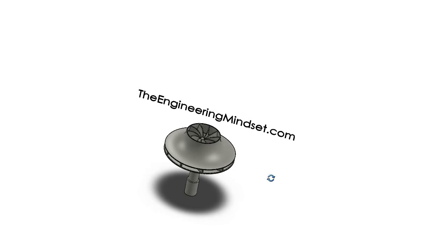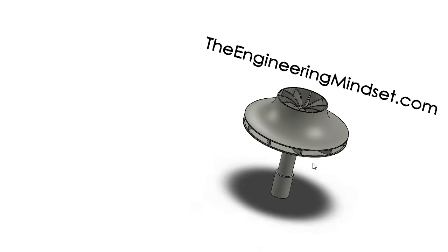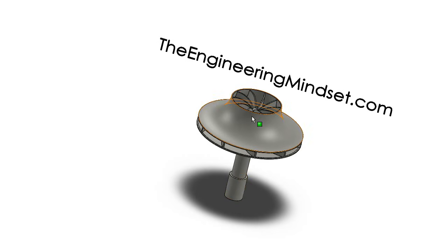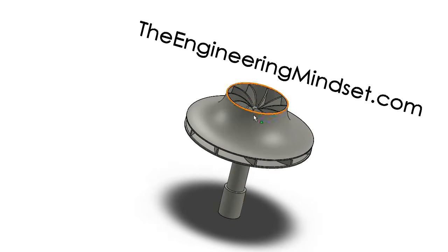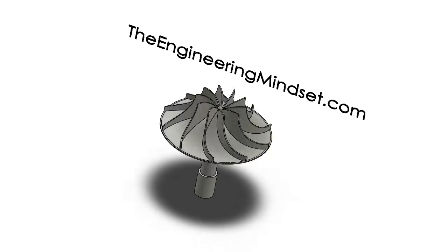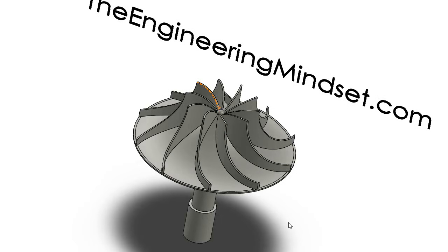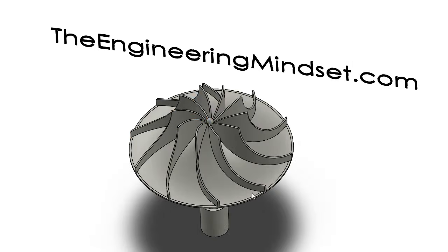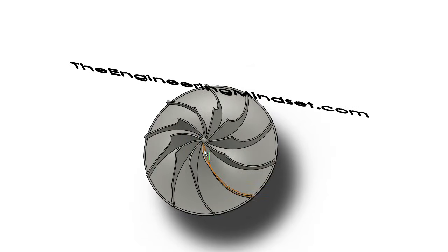If you look at the impeller here, so you can see we've got the gear mounted on the bottom of the shaft there, and at the top we've got the inlet or the flow area, and then we've got a shroud here, and then just hiding the blades behind it. And if I remove the shroud, you can just expose the blades there, and you can see the kind of shape they've got. So this will suck the refrigerant in, and it will divide the refrigerant that's coming in into equal portions and distribute that off through each of these blade discharge areas. And you can see it's a backwards inclined blade, which sends it off at a high velocity.